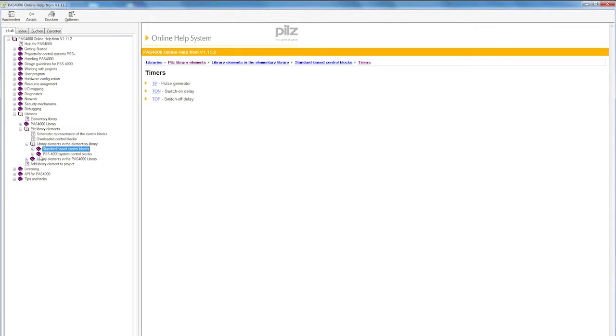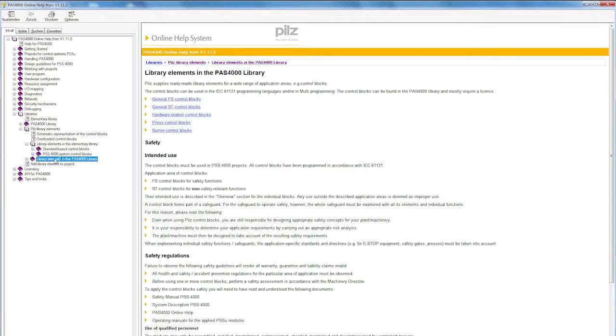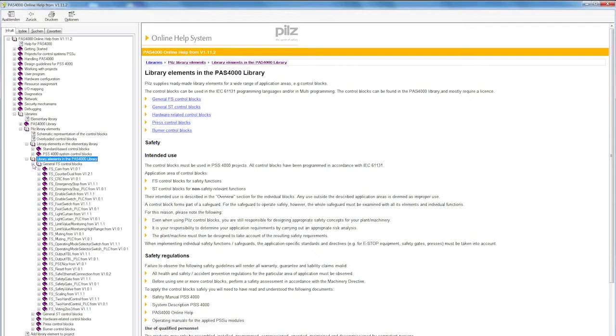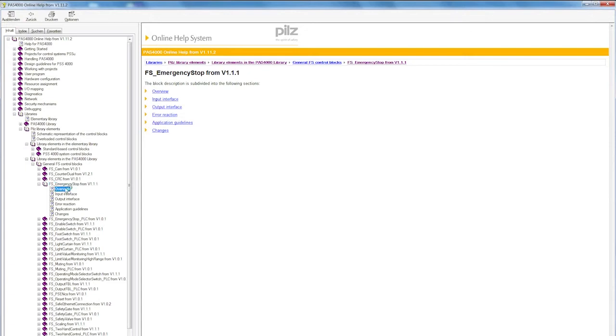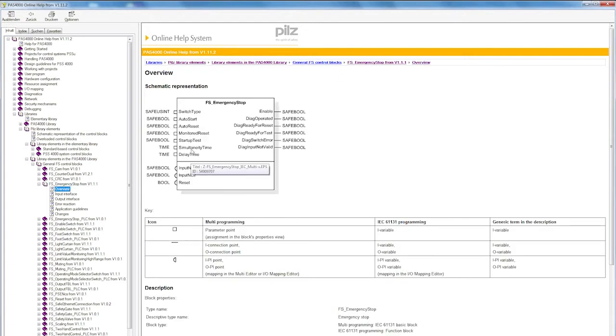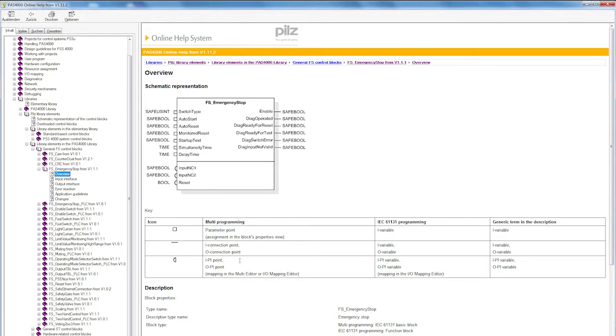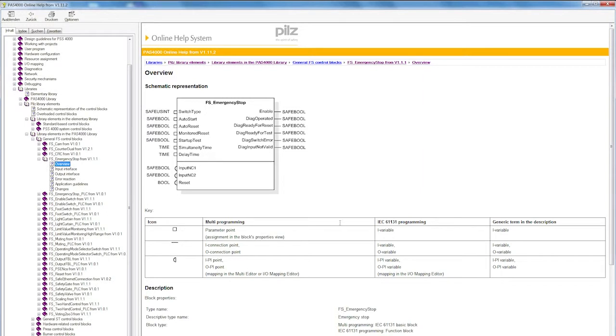Now I'd like to move my attention to the PAS4000 library, in which all our safety-related and non-safety-related function blocks are explained, such as emergency stop, for example. In the overview, there is a schematic representation of the emergency stop, with all input variables on the left and all output variables on the right. Down here you'll find the key to the symbols, what they are called in multi-programming, how they work in IEC 61131 programming, and a description of the block.